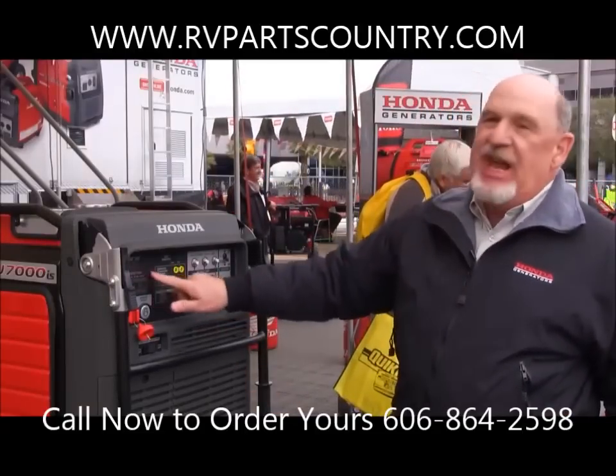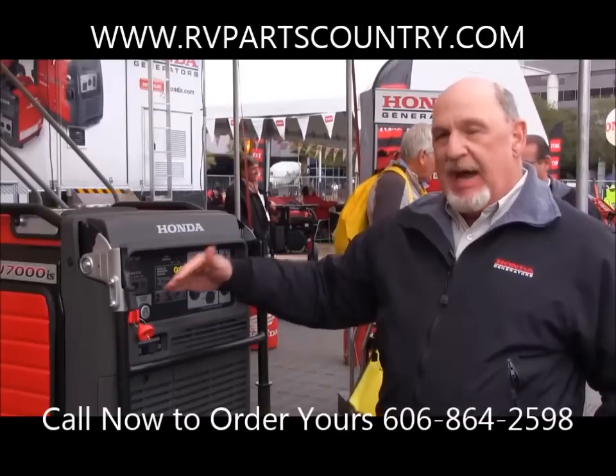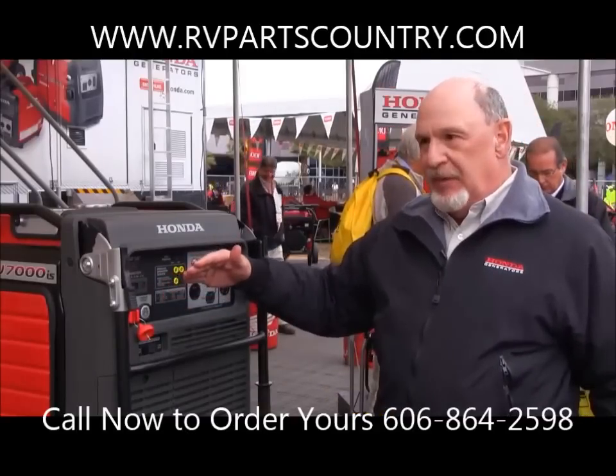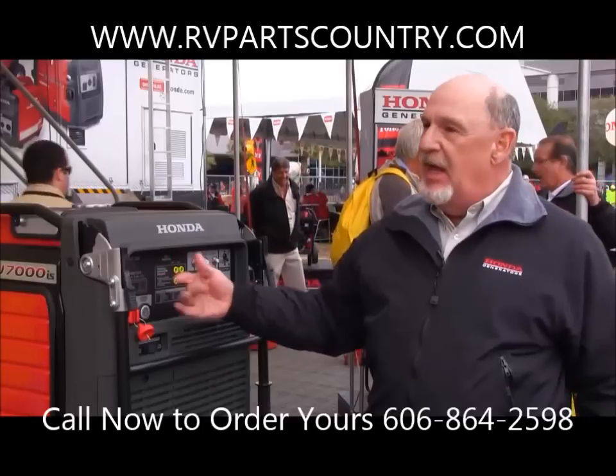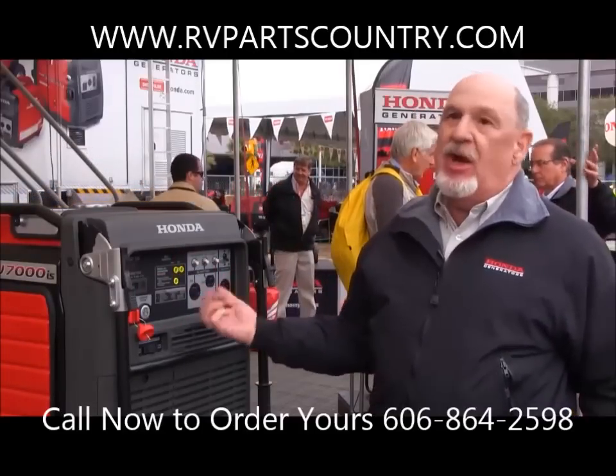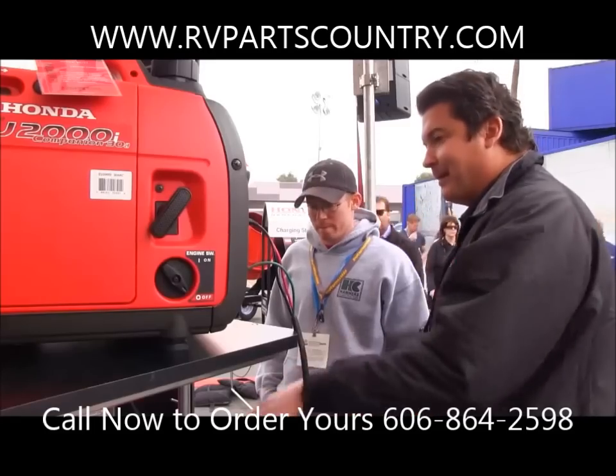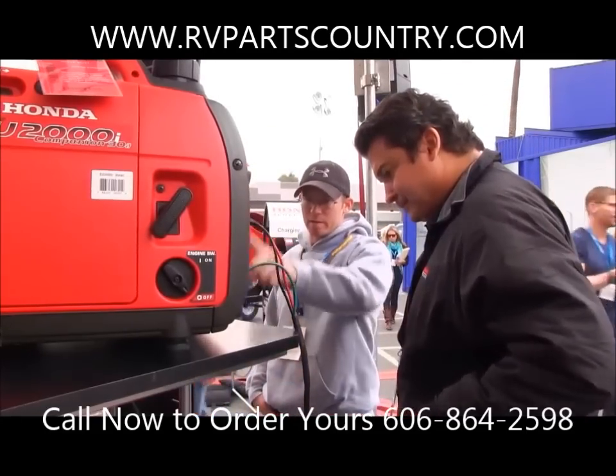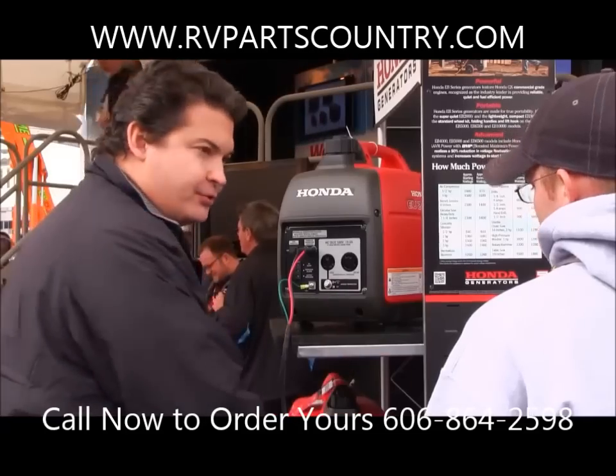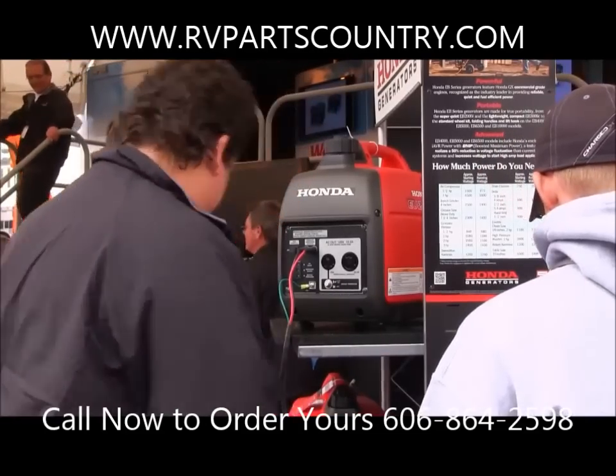This generator introduced the iMonitor system, which provides the customer with operational information — hours of use, actual performance, and demand on load. It also has onboard diagnostics, so if there's ever a failure, it will read a code for a technician or the customer to know: overloaded, overheated, or a component failure — for quick service and getting it back into service.